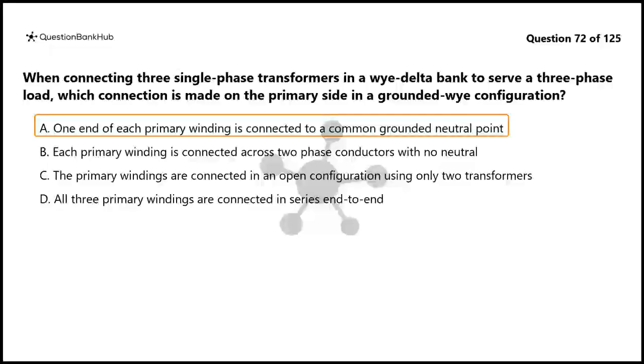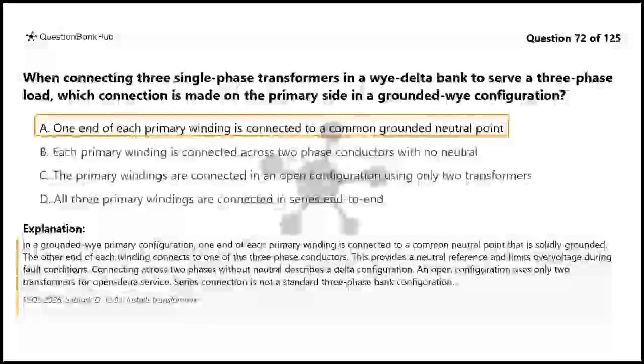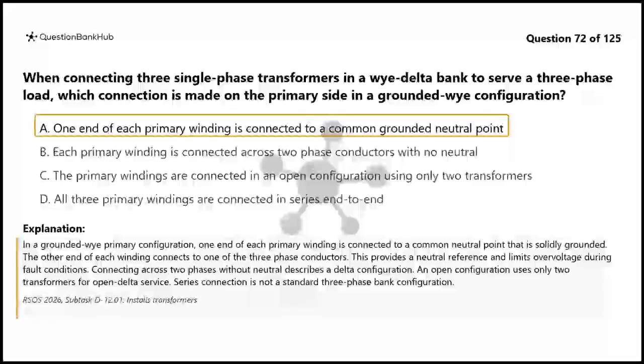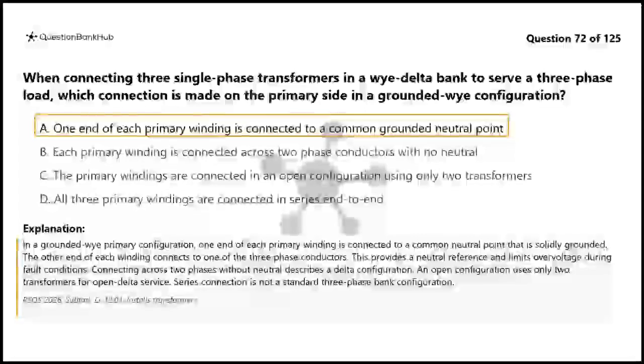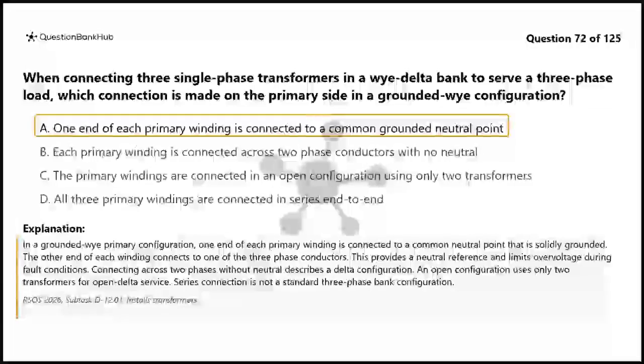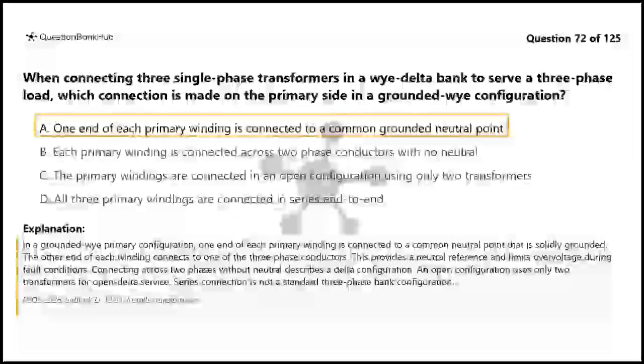The correct answer is A. In a grounded Y primary configuration, one end of each primary winding is connected to a common neutral point that is solidly grounded. The other end of each winding connects to one of the three-phase conductors. This provides a neutral reference and limits overvoltage during fault conditions.